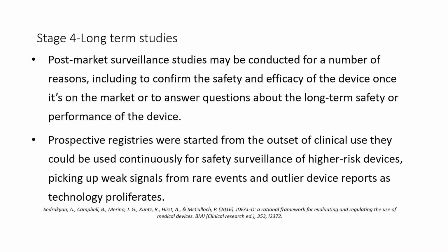Then we have stage 4, which deals with long-term studies, right, where you basically have post-market surveillance conducted for a number of reasons, including to confirm the safety and efficacy of the device once it is on the market, and to answer questions about long-term safety or performance of the device, right? So the long-term effects are also very, very important.